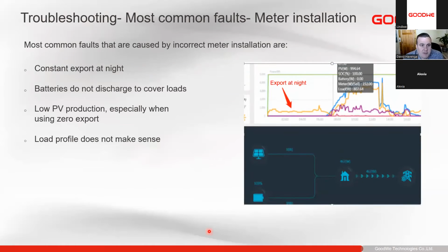So next, one of the most common things we have is the smart meter installation. So best to look, when we have no PV or no battery discharge, we can look at the graph. As you'll see, we have constant export at night. Obviously, there's no DC power being used, so we shouldn't be exporting. That's a good indication that the CTs are connected incorrectly. As well as for our hybrids, you'll see the batteries stay full all the time. They do not discharge because it has the logic that if we see something exporting, we use that export to charge the batteries.